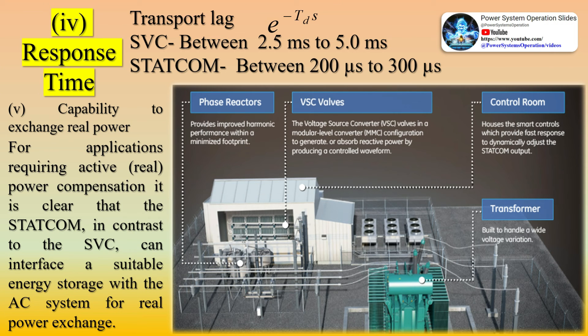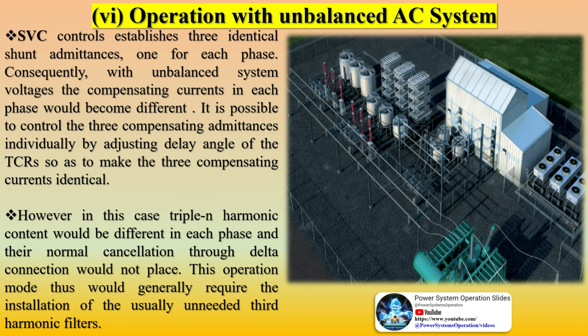The operation of the STATCOM under unbalanced system conditions is different from that of the SVC, but the consequences of such operation are similar. The STATCOM operation is governed by the fundamental physical law requiring that the net instantaneous power at the AC and DC terminals of the voltage-sourced converters employed must always be equal. This is because the converter has no internal energy storage, and thus energy transfer through it is absolutely direct; consequently the net instantaneous power at the AC and DC terminals must be equal.